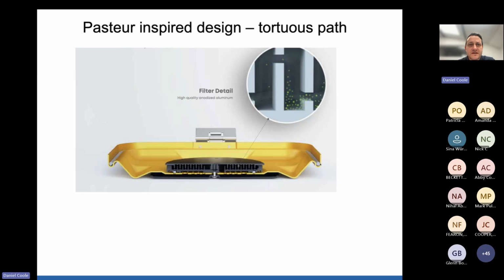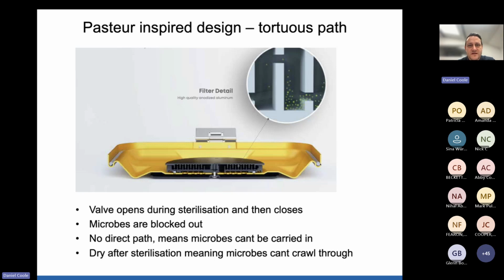As I've mentioned, the valve system. So this is inspired by Louis Pasteur's famous research. So we have a valve system that opens during sterilization and then closes. And you can see here what's described as the tortuous path, which prevents the microbes from traveling through. So obviously with this complex labyrinth, the microbes are blocked out. There's no direct path, which means the microbes can't be carried in. So it's actually a very simple system, but it means that you don't then need a paper filter or a PTFE filter that you've got to replace. You just have this barrier valve system, which then has validation for a particular amount of cycles. So after sterilization they dry, meaning the microbes then can't crawl through as well. Any questions around these as we go along, please chuck it in the chat and I'll pick up at the end.